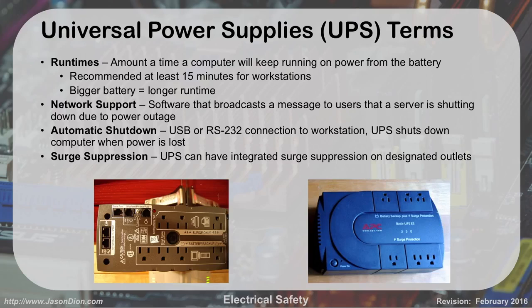It gives everybody a warning because now the domain controller or the file share is going to go down. A lot of UPSs have automatic shutdown. If you have your personal computer, many UPSs, like this one on the right, have a USB port that plugs into your computer. If it detects that the power went out on the wall, it's providing battery power to your computer still, but it sends a message saying, hey, we lost power, so I'm going to shut you down. That way the computer can do a safe shutdown instead of having the power yanked away. Because we can't run off the UPS forever, we only have 10 or 15 minutes worth of time. And then we have surge suppression.